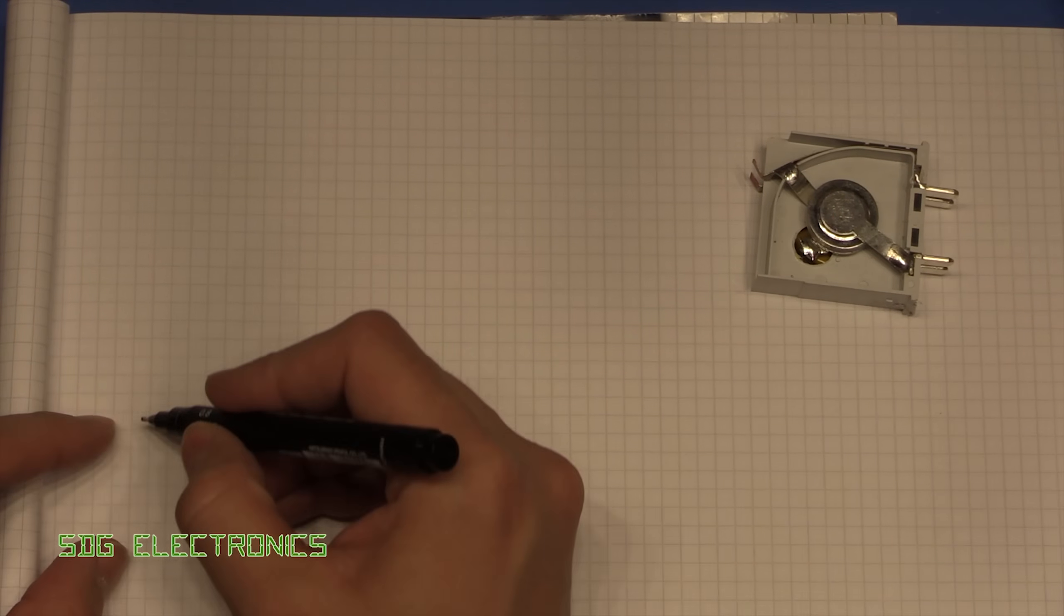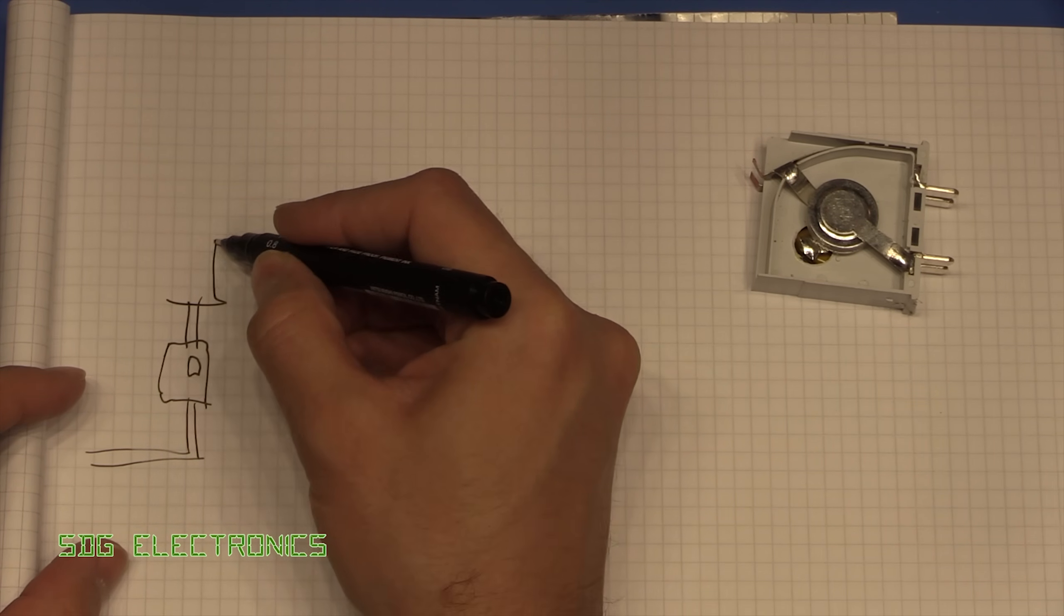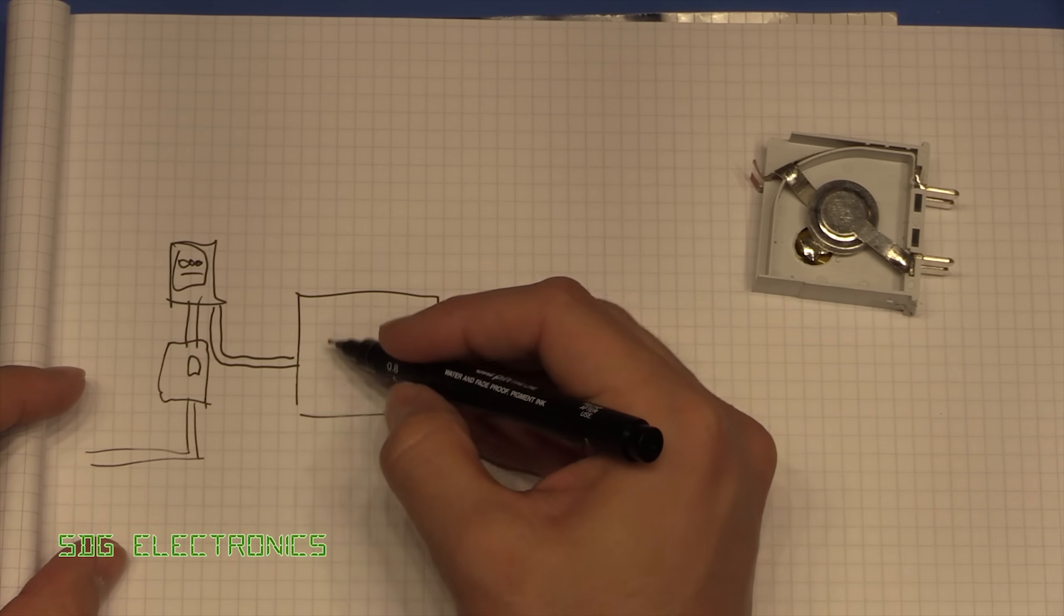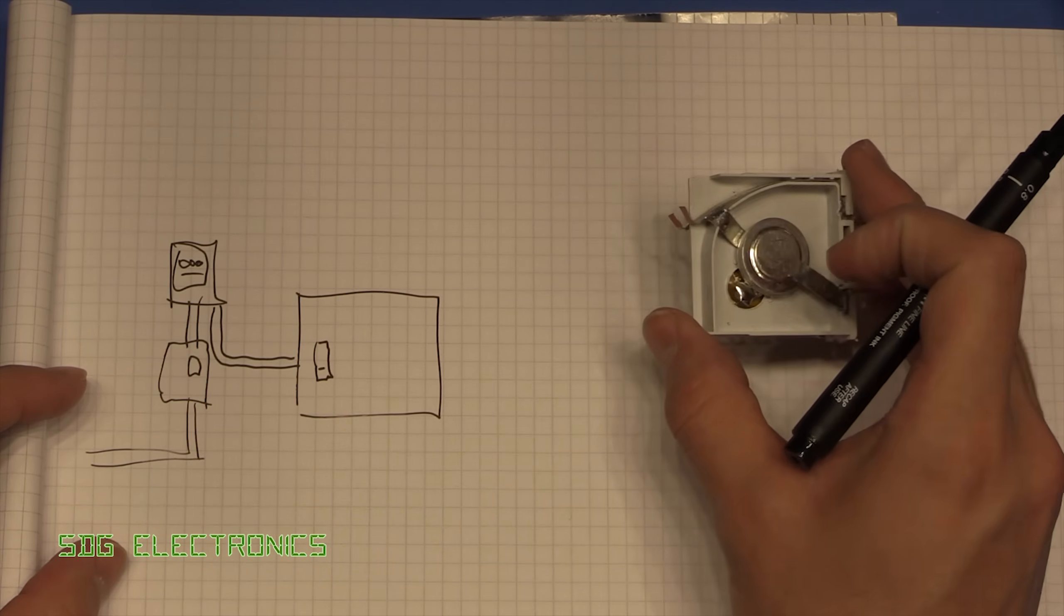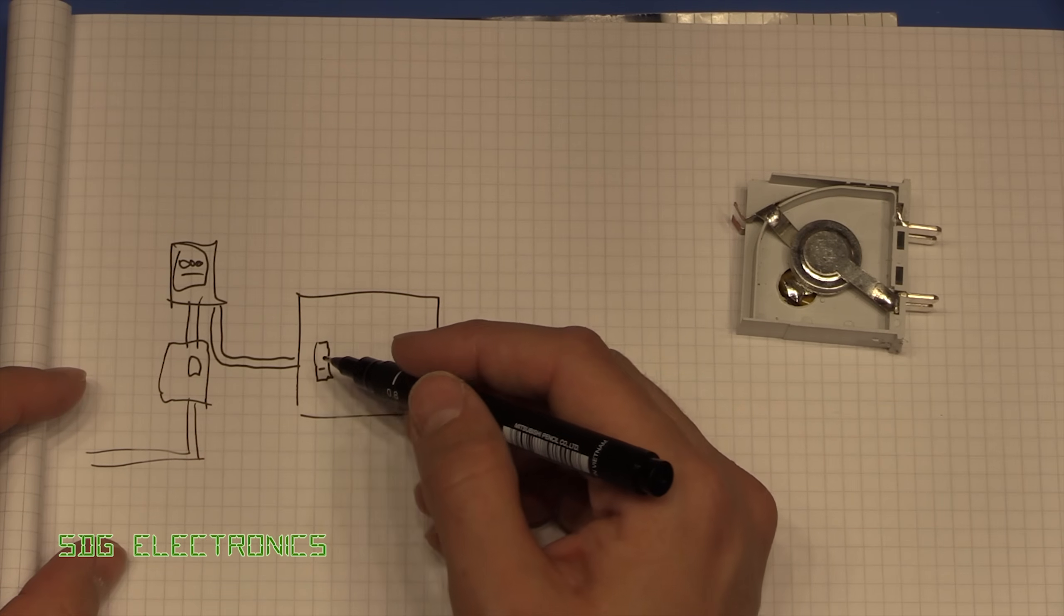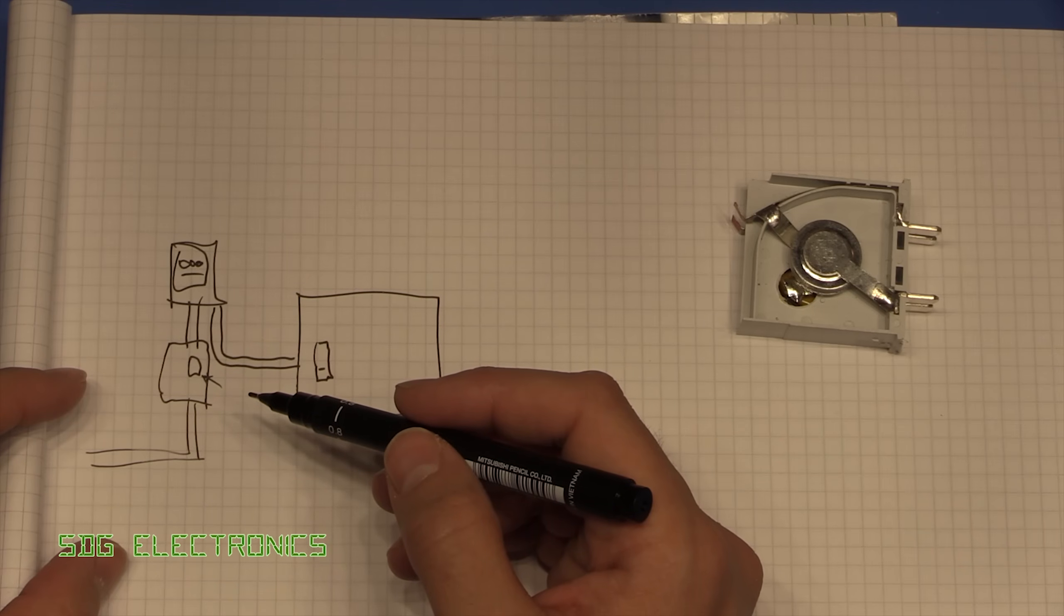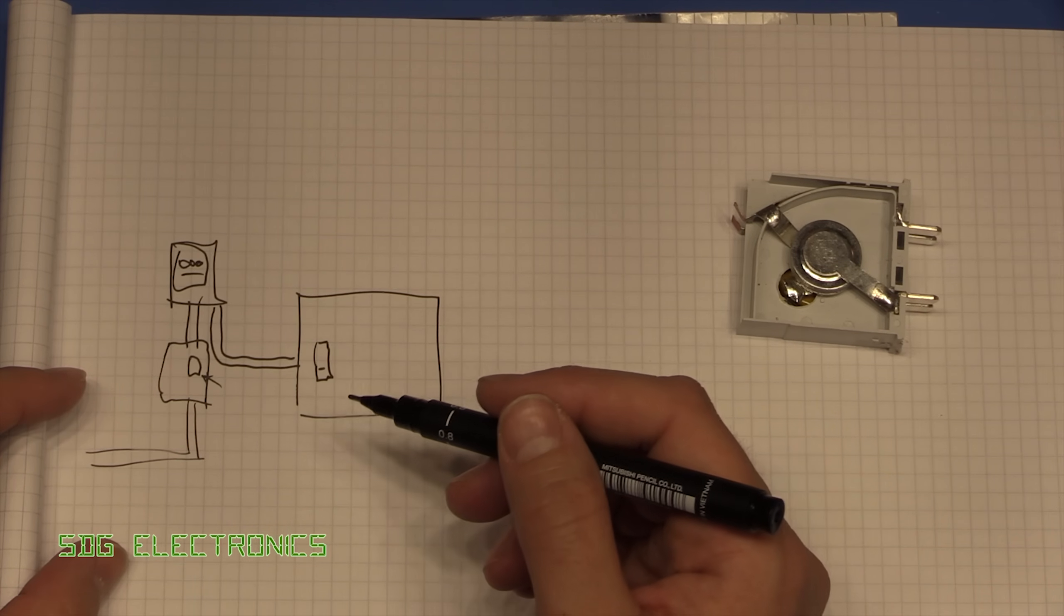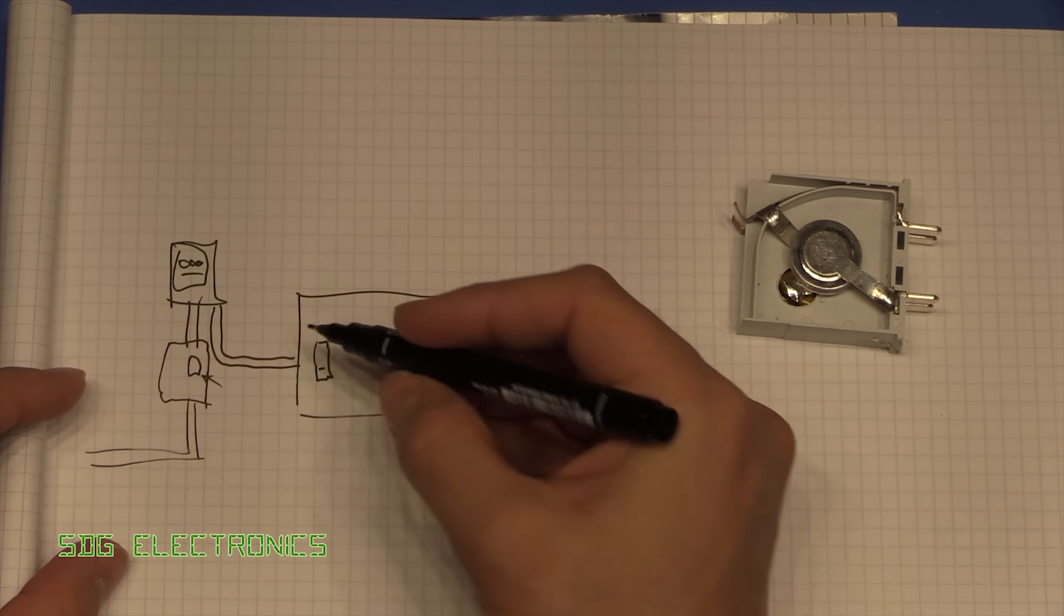Right, so the way that you connect this device up is you've got your incoming main supply, it goes into the main service head and passes to the meter, so we've got a meter here with all the dials on, and then this passes through to the consumer unit. The way that you typically install this is you've got your main switch on the side of the consumer unit. What they would recommend that you do is provide some overcurrent protection, so this doesn't just catch fire, because the main switch on these consumer units is purely an isolation device, it has no overcurrent protection. Prior to this, the only protection you've got here is the 60, 80 or 100 amp service fuse, which actually will blow up considerably more than that. They don't blow - the 60 amp fuse isn't going to blow when you draw 61 amps, it would probably blow after some sustained period of 80 or 100 amps. It's basically a piece of wire that heats up and that's going to take time to heat up to the point where it's going to melt.